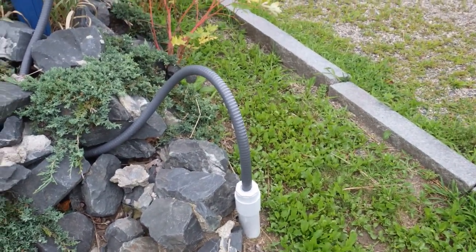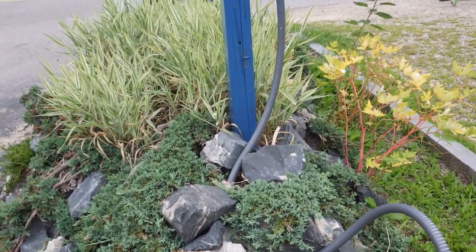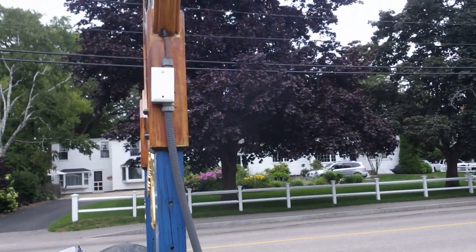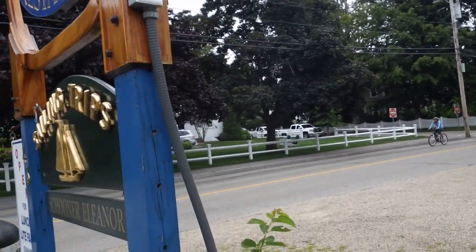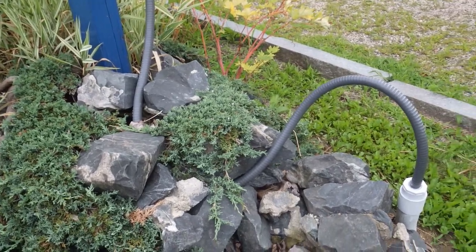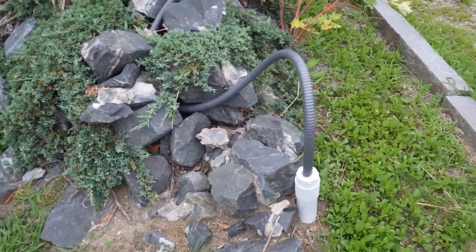Hello, it's Russell Blank, NEC Consultant here for EC&M Magazine, and we're taking a look at this liquidtight flexible non-metallic conduit that we see. This is wiring for a sign here, and it's just kind of flopping in the breeze. It comes off the box totally unsupported, buried by some rocks, and then it's just stubbed into what looks like plumbing PVC going underground.